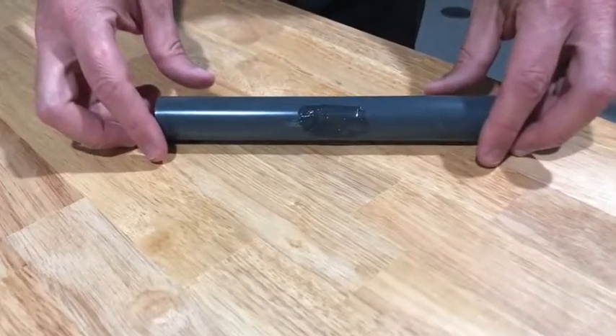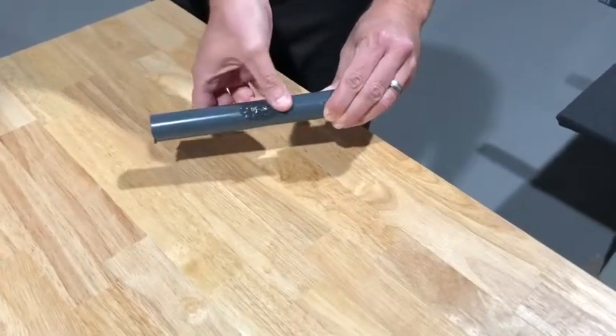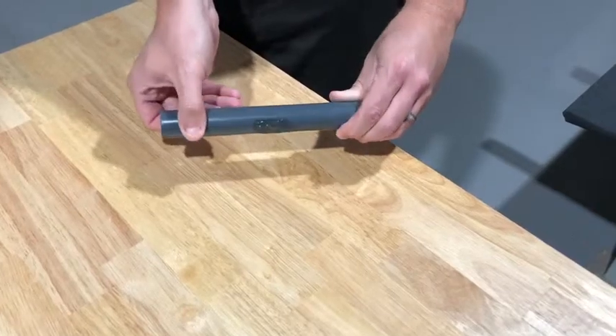The PVC coating repair kit epoxy sets in six minutes and cures in three to four hours, to a dark gray color that matches Plasti-Bond's PVC coating.